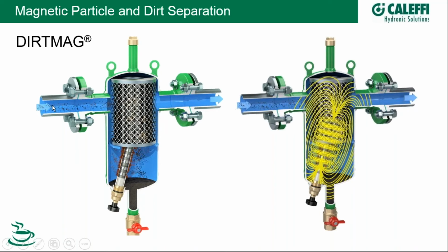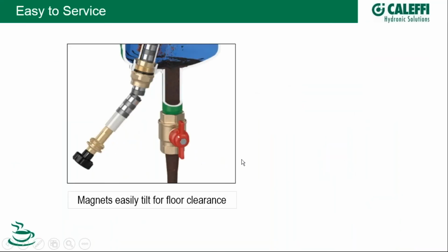So that tricky magnetite that's so small, even though it's denser than water and you think it might fall down, gets carried in a fluid path very easily and continues on in the system, only to find itself in a place that it shouldn't, creating problems like I showed you in that previous slide. And so that's why there are magnetic separators. They articulate as you service the separator. When you're going to blow it down, you pull the magnet out, and if you have no clearance in your floor, they'll articulate like this to give you the floor clearance. So, nice design by our engineers.